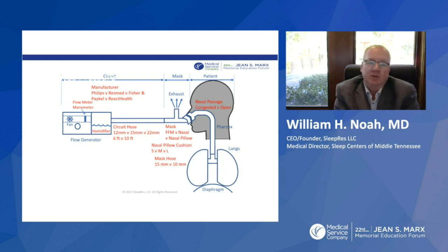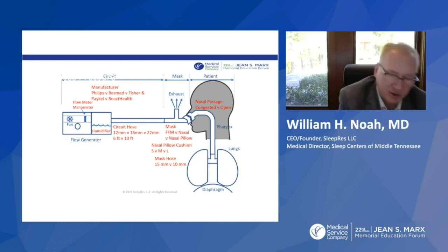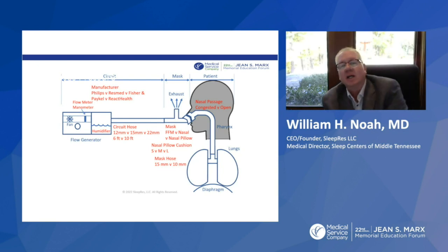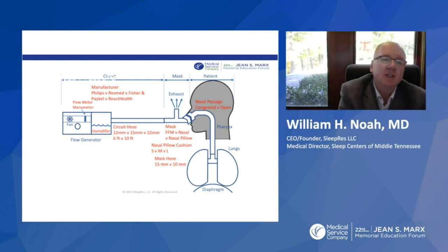Obviously, the mask hose, some of these mask hoses now have a 10 millimeter diameter, and that's going to create tremendous resistance. We don't talk about inside the body. The nasal passage is going to create resistance and pressure drop, particularly if they're congested. And of course, it depends what type of mask you're on. Because a Philips mask, if the large and medium cushion have much more resistance than a ResMed or Fisher & Paykel or React Health mask. And the small cushion, it's about the same.